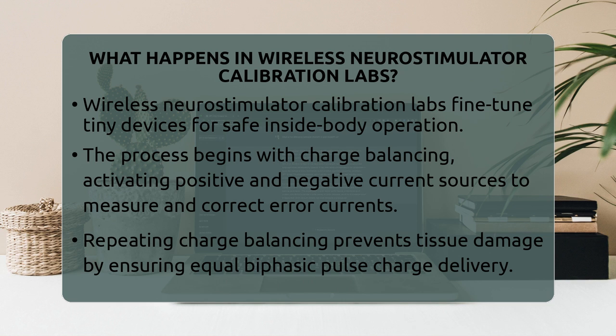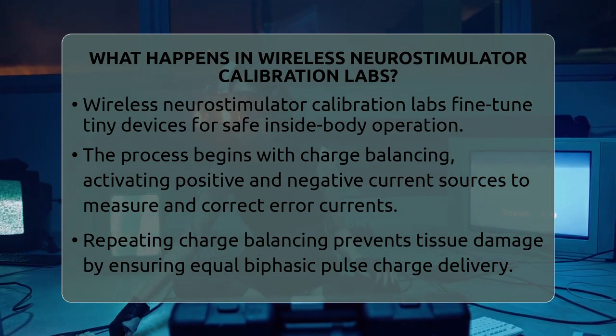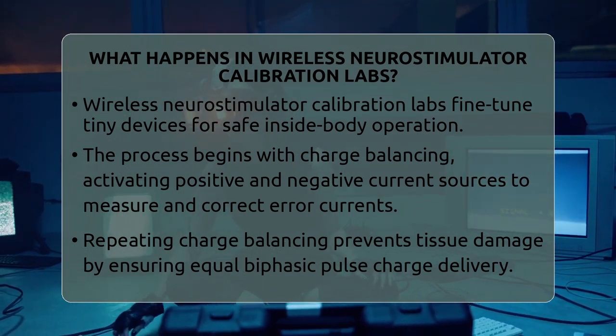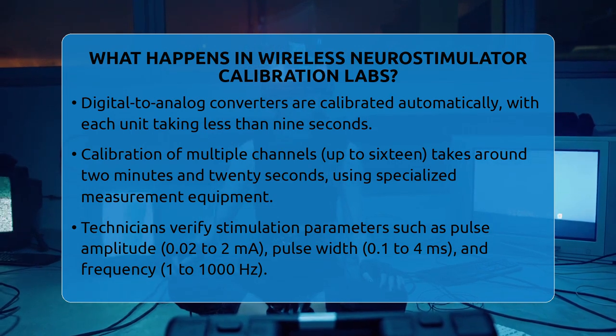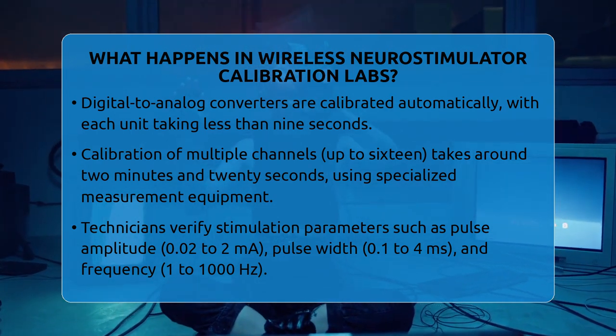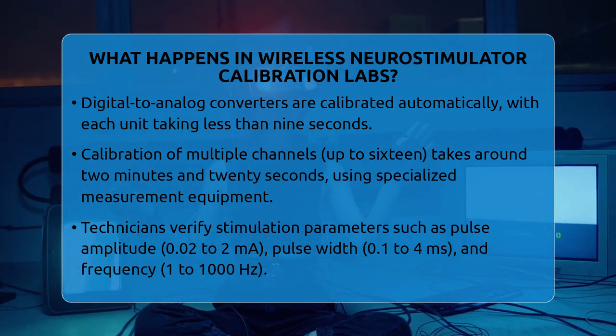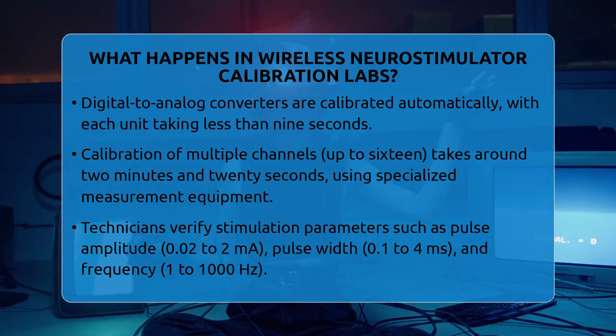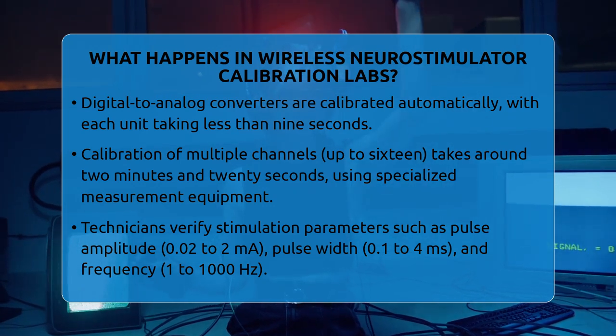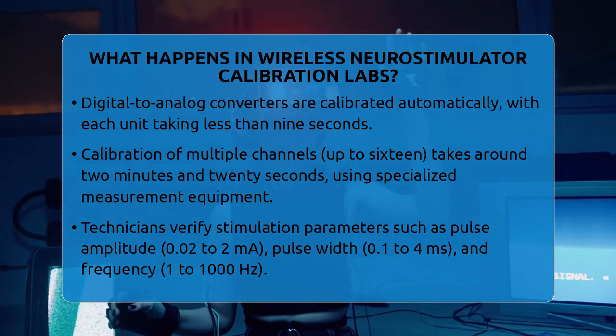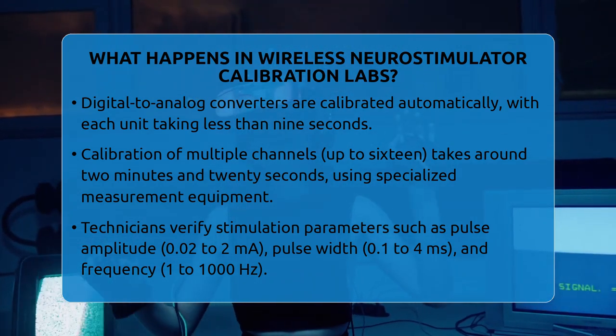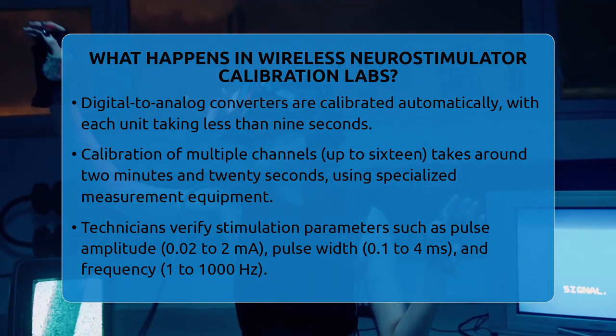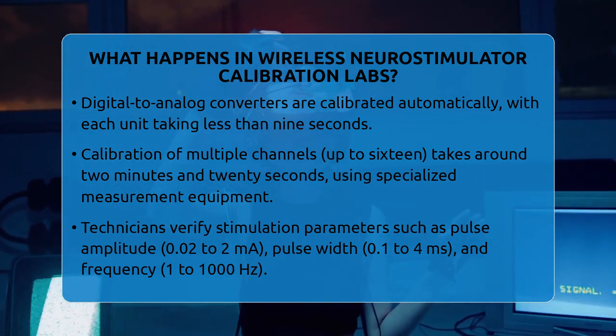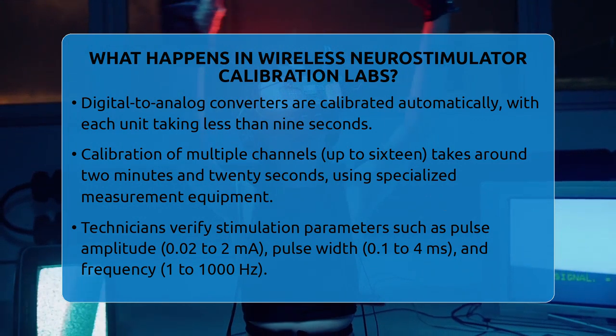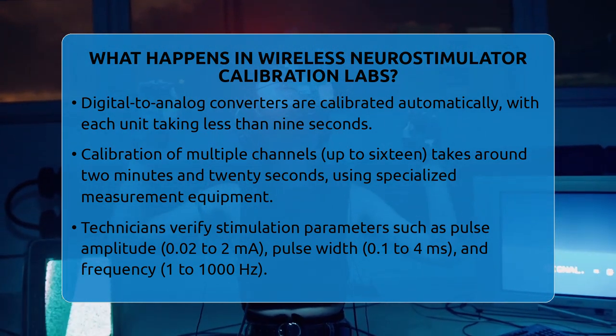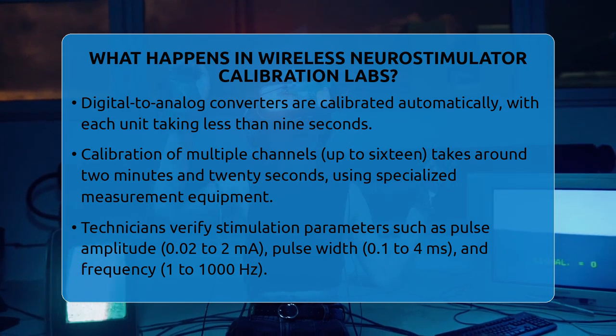Next, calibration of digital to analog converters is performed. These components turn digital signals into precise electrical currents. Advanced systems use sub-binary radix digital to analog converters, which are calibrated automatically. Each calibration takes less than 9 seconds for a single converter. When calibrating a full set of 16 channels, it takes about 2 minutes and 20 seconds. Specialized equipment, like source measurement units, measure the current during this process. These measurements can range from microseconds to tens of milliseconds, depending on how precise the calibration needs to be.